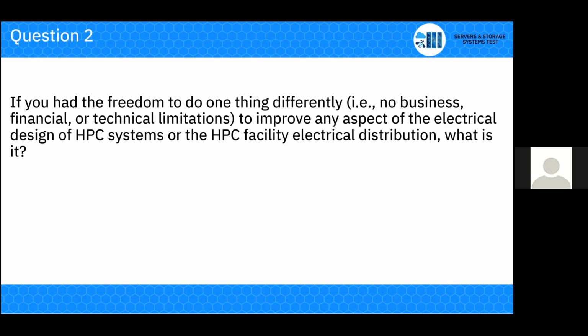Okay, I want to change the perspective. If I were a distribution or transmission grid operator, what would I appreciate being implemented at an HPC system? First would be more load balancing, similar to what Herbert mentioned - storage devices able to flatten the consumption curve, which is very important for the grid operator. Next is power quality: grid operators want stable voltage and minimized impact on overall power quality, meaning additional devices to stabilize voltage, such as static VAR compensators or dynamic voltage restorers, which can flatten voltage volatility.